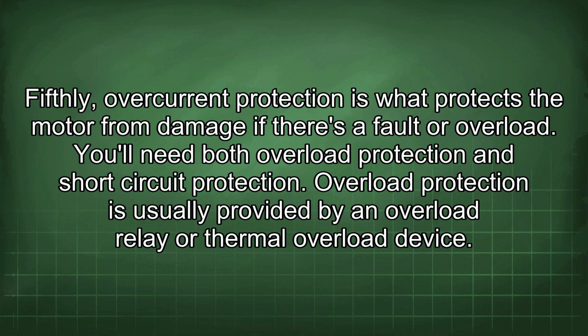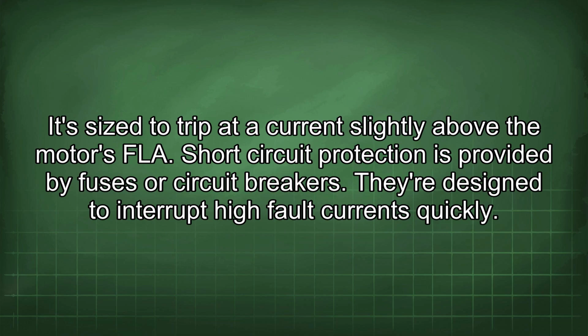You'll need both overload protection and short circuit protection. Overload protection is usually provided by an overload relay or thermal overload device. It's sized to trip at a current slightly above the motor's FLA. Short circuit protection is provided by fuses or circuit breakers. They're designed to interrupt high fault currents quickly.